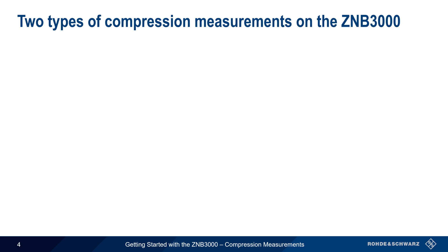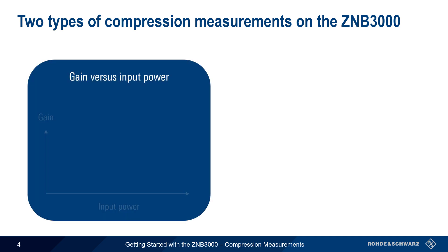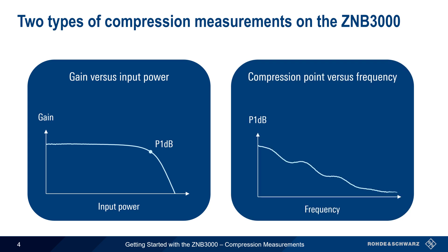Two types of compression measurements are supported on the ZNB3000. The first is the standard gain versus input power measurement, made at a user-defined fixed frequency. Generally speaking, these types of gain compression results will have a shape similar to the one shown here. The other type is a 2D measurement showing compression point as a function of frequency. It's not uncommon for a compression point to be different at different frequencies, but the shape of this curve will vary by device.